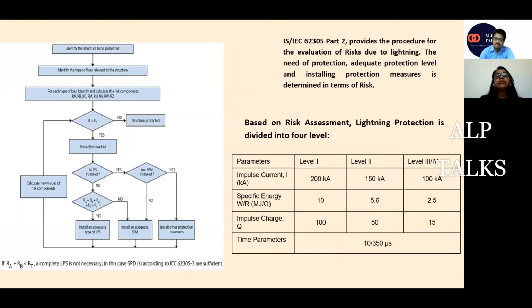I mean, do the bridges also need to be protected from lightning? Everything, be it foot-over bridges, flyovers, bridges, temples, mosques, everything needs to be protected from lightning strikes. If it is a normal road, we don't do it. For normal roads, we have street light poles, so we generally use them for the lightning protection system, or we install air terminals over them. Even the traffic lights and CCTV poles which we have nowadays on the highways and flyovers are also protected with the lightning protection system. The authorities and departments are so concerned that everything should be protected with it.